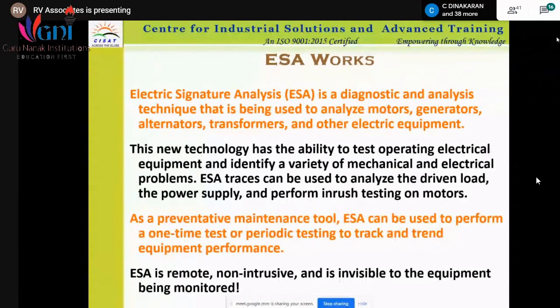Like if bearing failure is there, which particular part has failed? Or if there is a winding failure, which winding is failing, or what is the reason for the failure? That complete analysis is done by the signature analysis. It is also called torque analysis, and it is an online tool. What we do is connect a CT to the stator winding, or the primary of the motor, and continuous monitoring is done, because when a fault is there, the pattern changes, and that pattern is analyzed by the software.